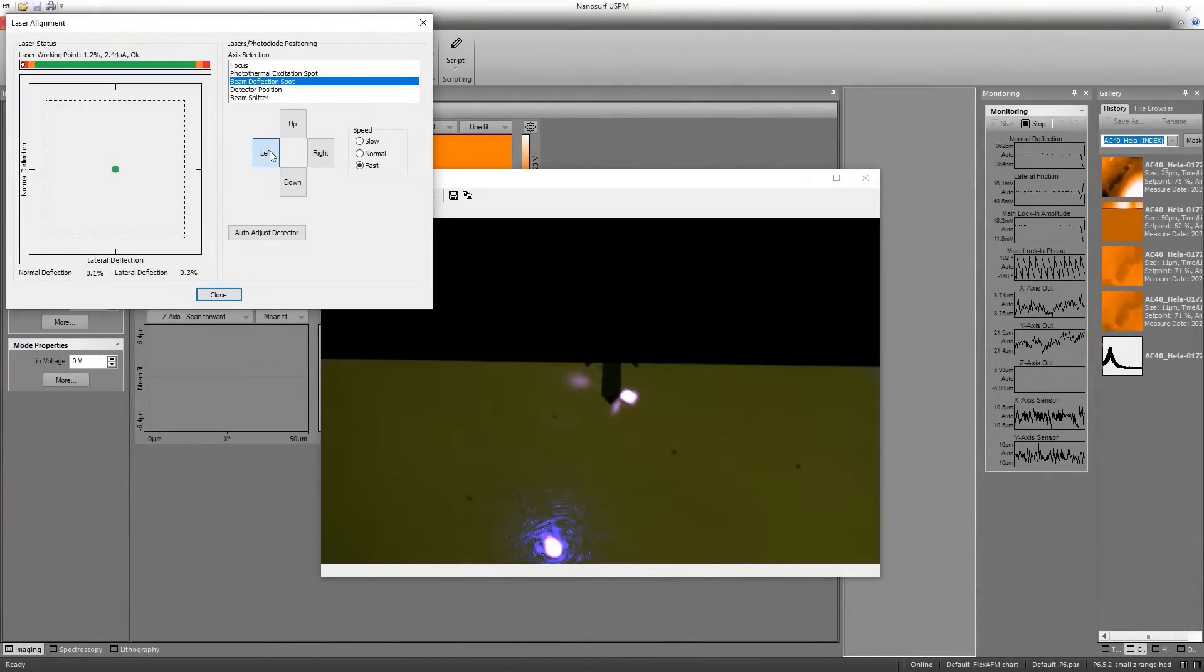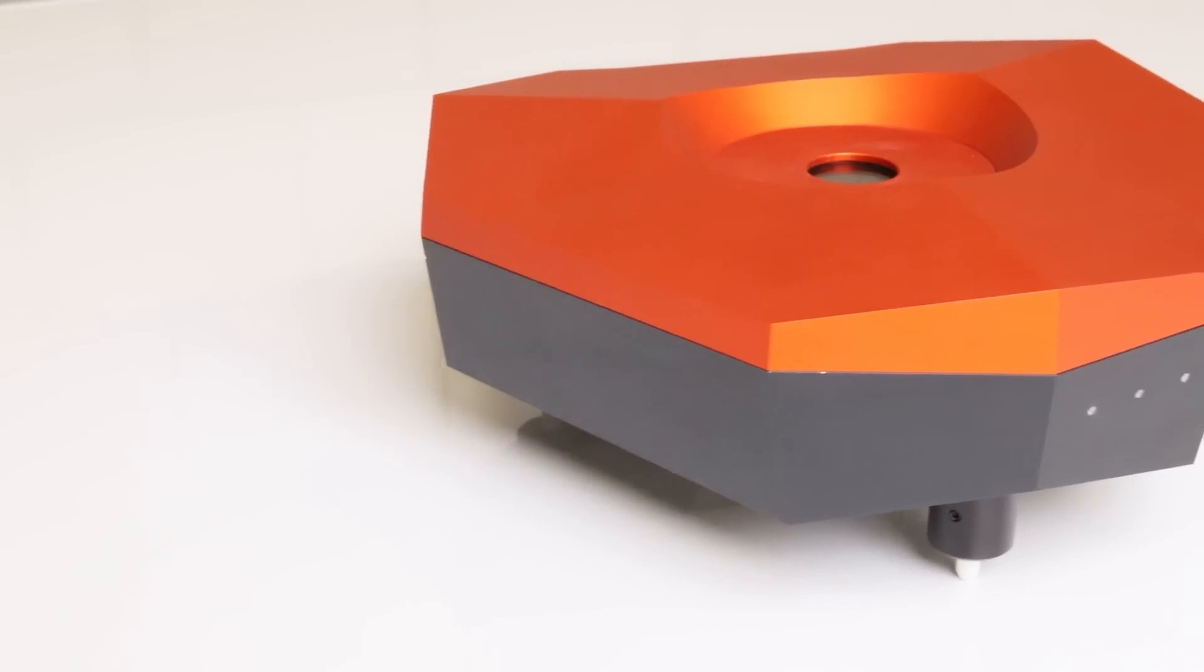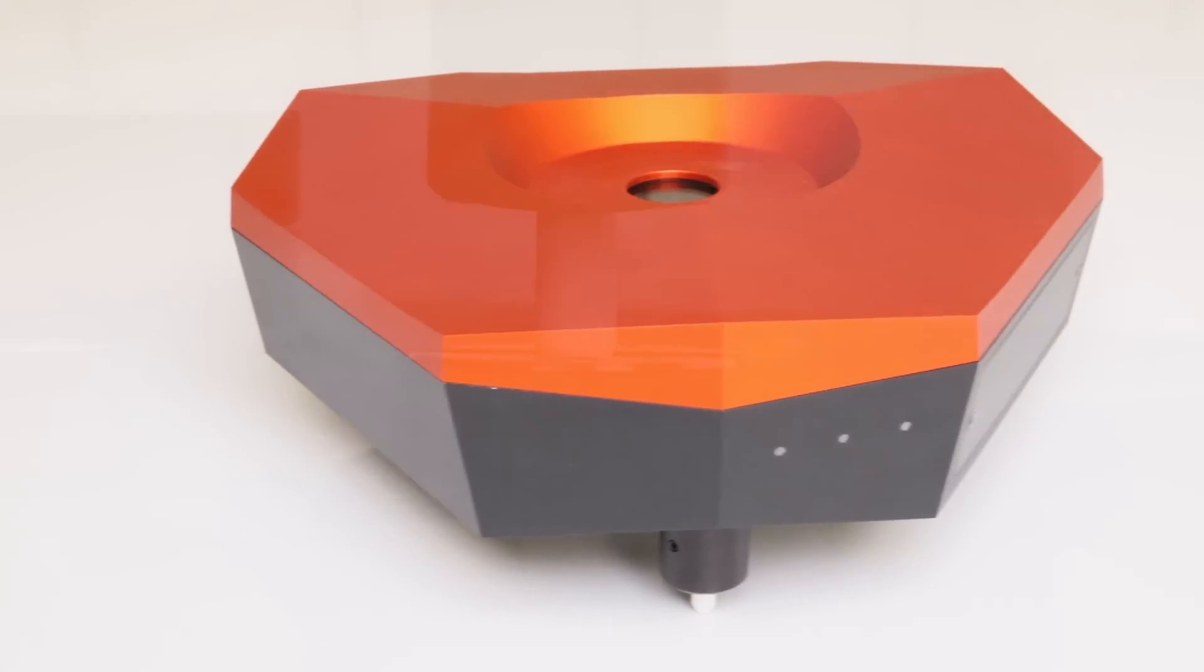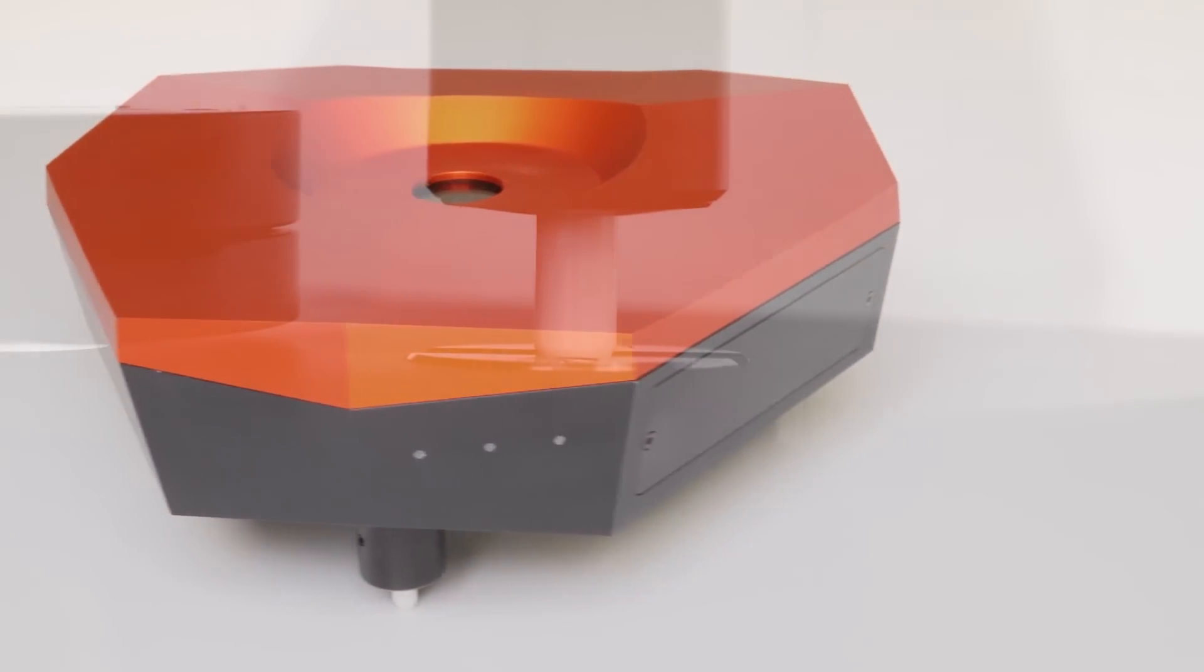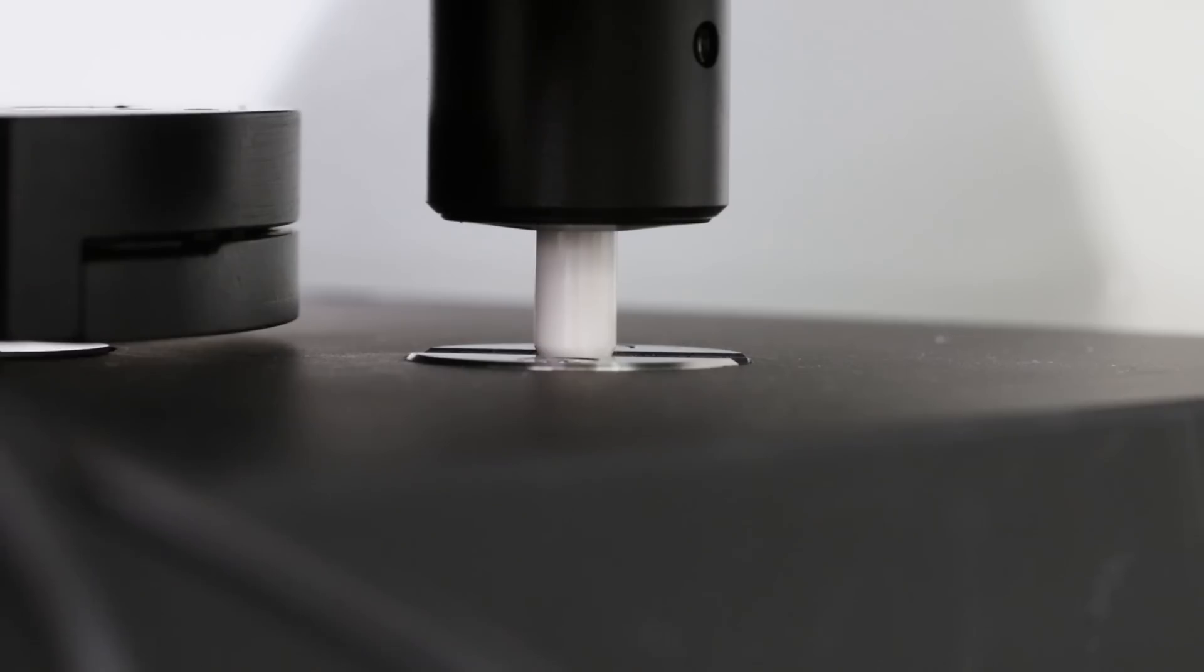First of all, there is the full motorization of this instrument. That means there's no knob that we have to touch at all. Everything is motorized. The laser detection system is motorized. The adjustment of the photo detector is motorized. Approach is motorized. The stage is fully motorized. Everything can be remotely controlled from the computer. You don't have to open the enclosure anymore.